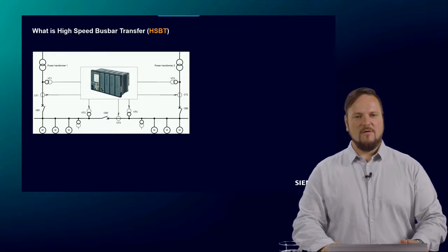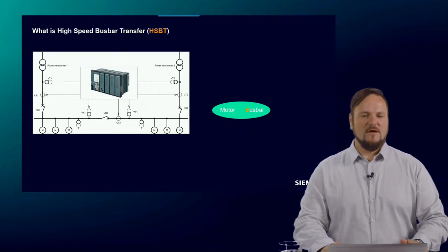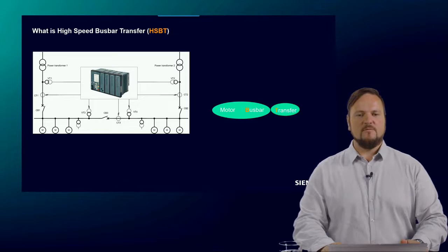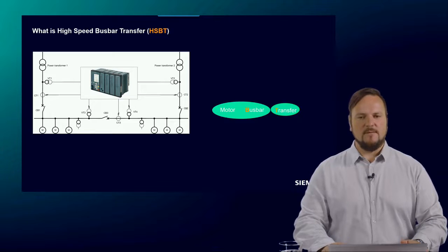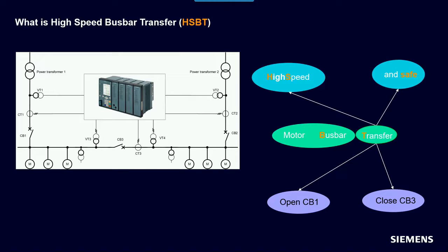Coming to my first slide, we talk about the high-speed bus bar transfer — HSBT device. That means we have a motor bus where inductive motors are connected, and we want to transfer the motor load from one incomer to the other. This requires opening CB1 on the left side and closing CB3 on the right side, but this interaction needs to happen in a very fast — high-speed — time. A second requirement for the HSBT is a safe transfer, meaning uninterrupted power supply for the whole factory.